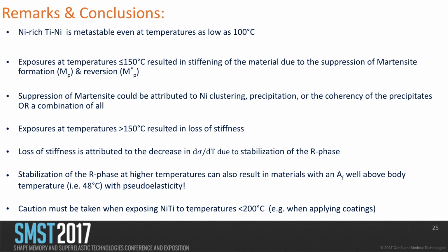And because of the stabilization of R phase, we can have nitinol material that has AF well above body temperature and still be superelastic. And the last one is we have to be careful when we expose nitinol to temperatures around 200 C. And that's it. Any questions?